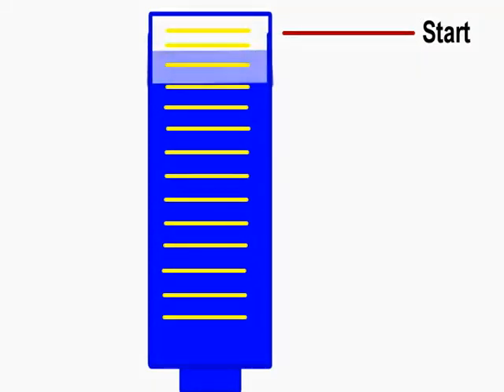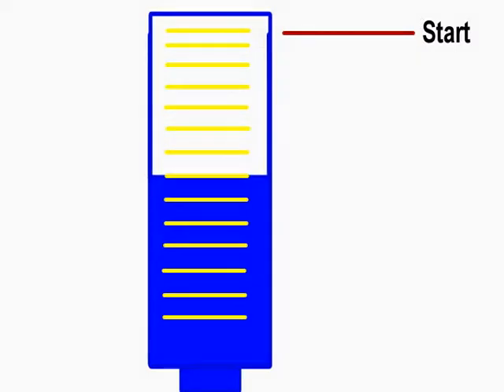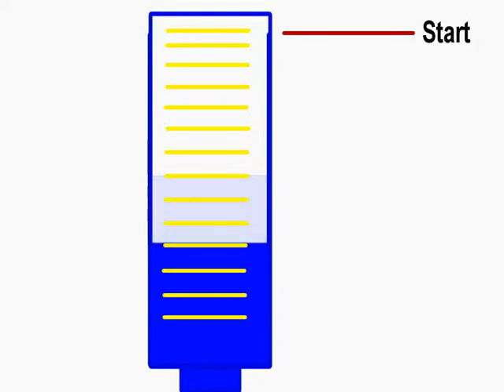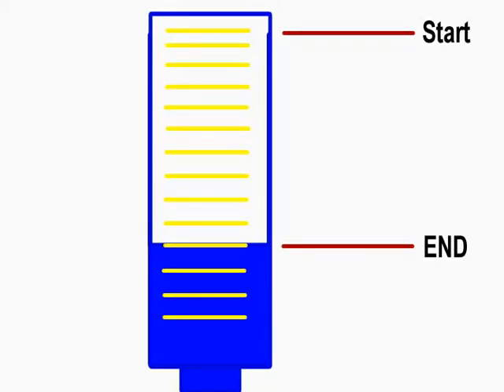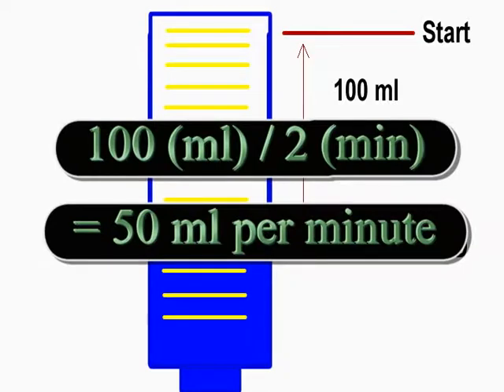Time the pump for two to three minutes. The longer time at the lower stroke settings gives the pump time to become consistent and compensates for any minor glitches the pump may experience. At the end of the designated time, mark the level in the tube and subtract the difference from the starting level. Divide the difference by the number of minutes the test was run to get the milliliters per minute flow rate.